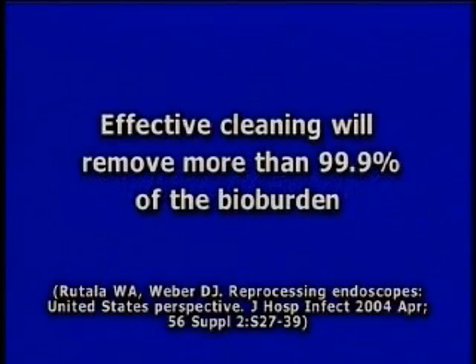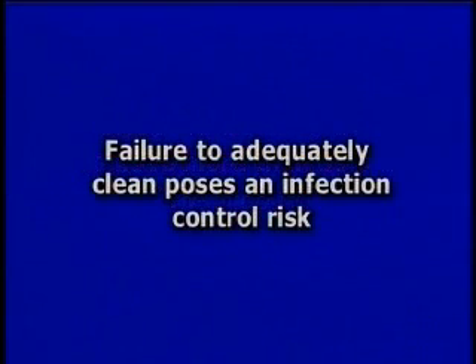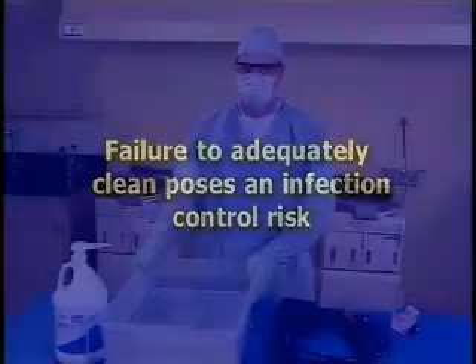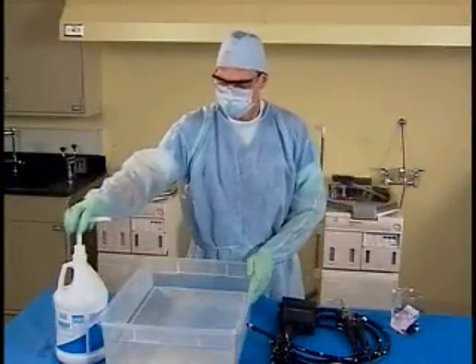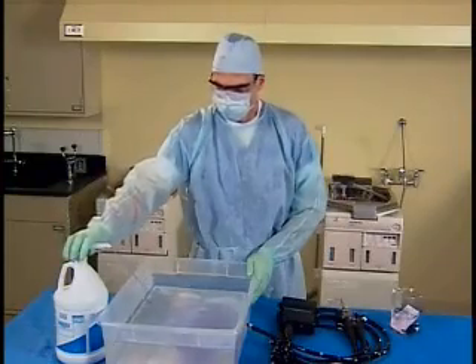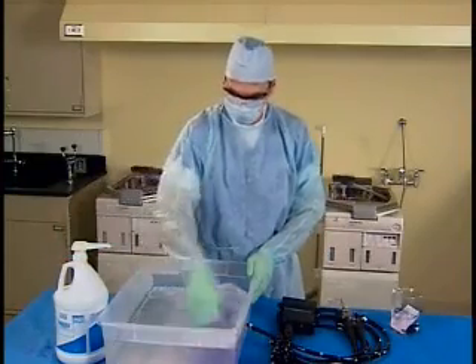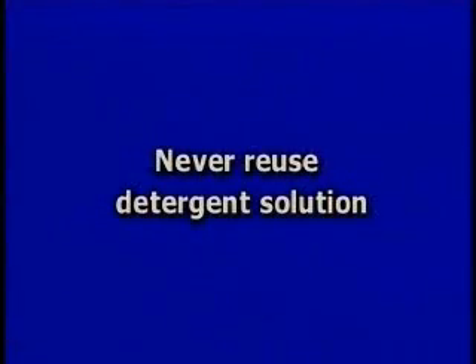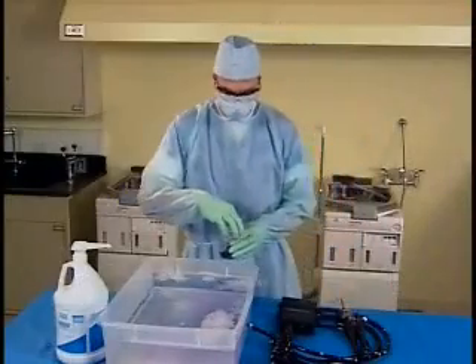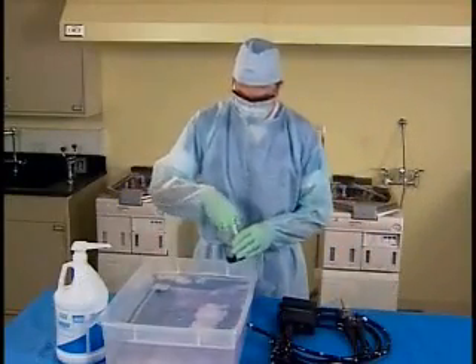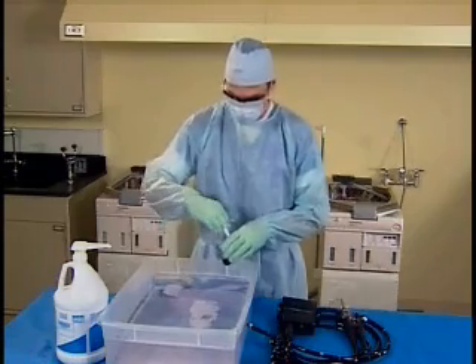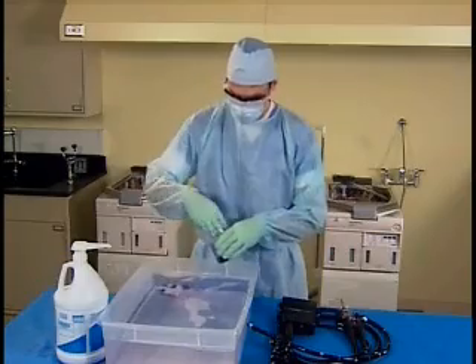Effective cleaning will remove more than 99% of the bioburden from the endoscope. Failure to adequately clean the endoscope will reduce the efficacy of any high-level disinfection or sterilization procedure which follows, and poses an infection control risk. Prepare a basin of detergent solution. Always use freshly prepared detergent at the specified concentration. Never reuse detergent solution. Remove the air-water channel cleaning adapter, the suction valve, and the biopsy valve, and place these items in the detergent solution.